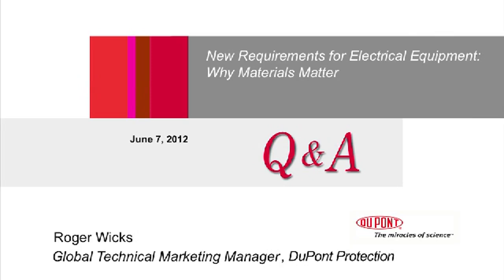Thank you, Roger. Here's a question. Does DuPont make any oil application insulation? Can we use type 418 for oil immersed transformers? Classically, either type 410 or type 414 papers are used in liquid immersed transformers. I believe there has been some use of 418. The concern there is that the mica platelets that are used as part of the 418 paper are not as tightly bound as might be necessary in that application, and they could come loose and float in the liquid stream, which could cause a problem. So I wouldn't necessarily recommend the use of 418 in a liquid-filled application. That would be something we'd want to study and investigate with the specific manufacturer to make sure it was okay.